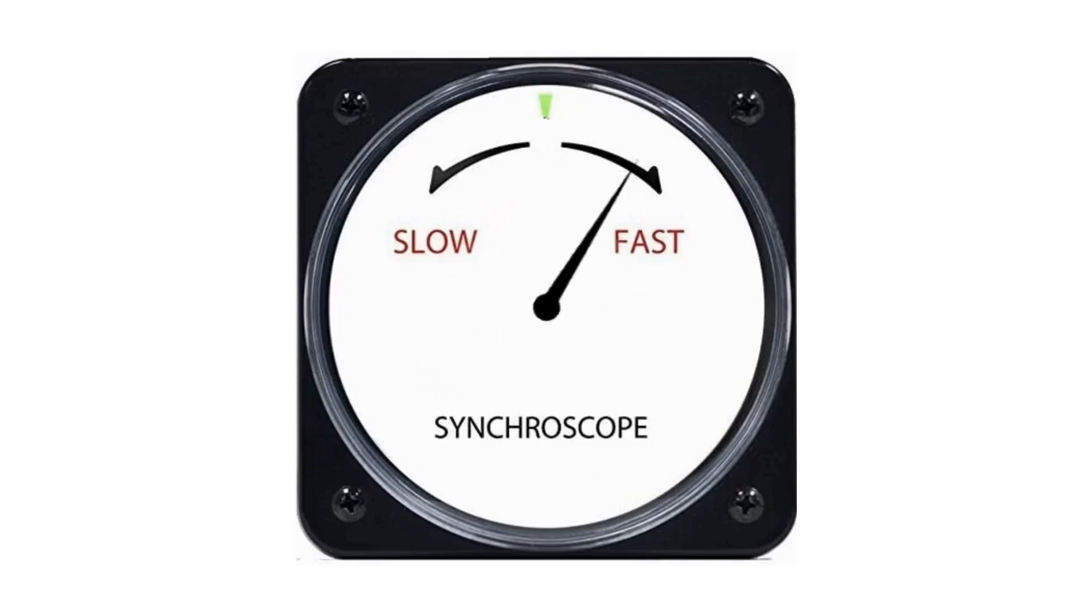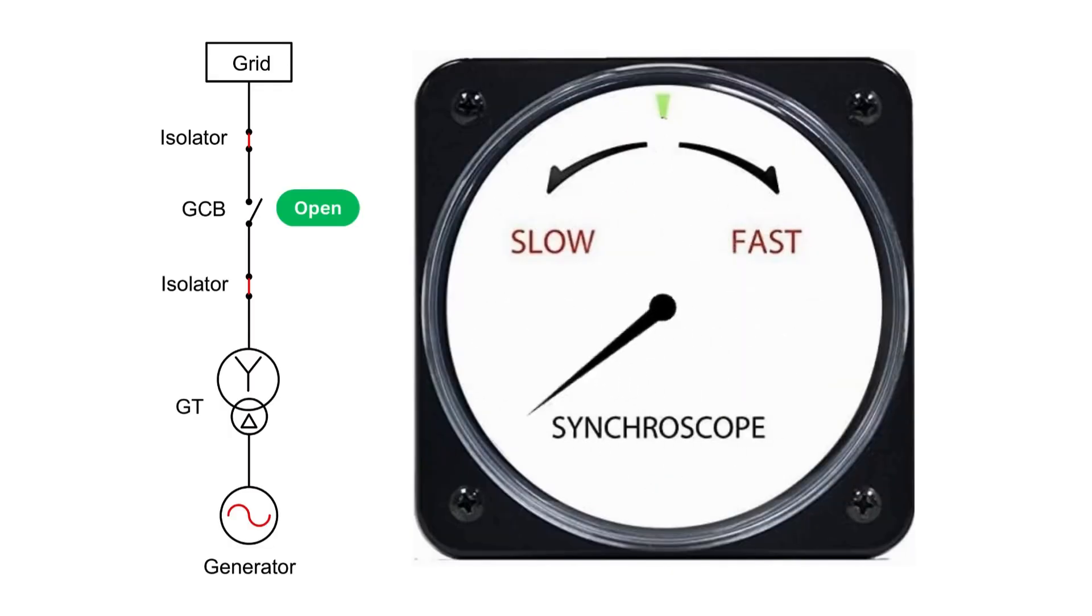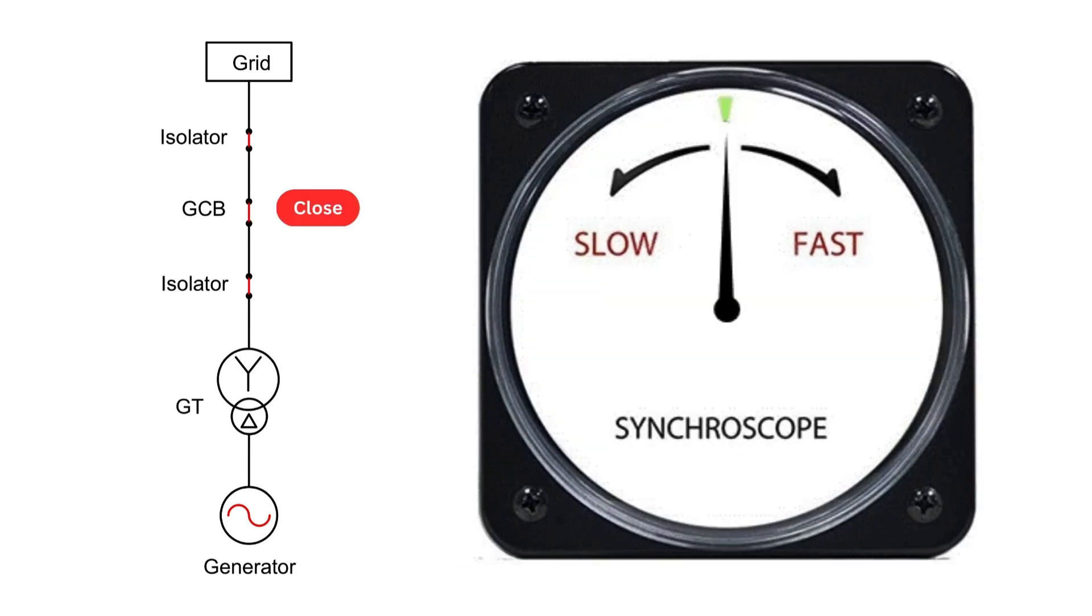The main role in this process is played by the synchroscope, which control room engineers monitor closely. As the synchroscope needle moves and reaches the 12 o'clock position, the operator gives a close command to the GCB or generator circuit breaker.